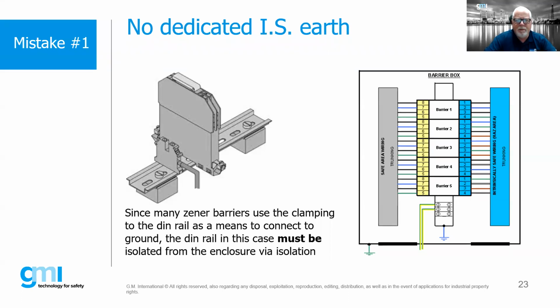then we can induce a potential fault condition into it. So we'd disconnect one of the legs of our clean earth, do a test, and find out whether we are getting that 1 ohm resistance or less. If we're good, we reattach it, then disconnect the other one and do the same test on that one. So it's a redundant earth.